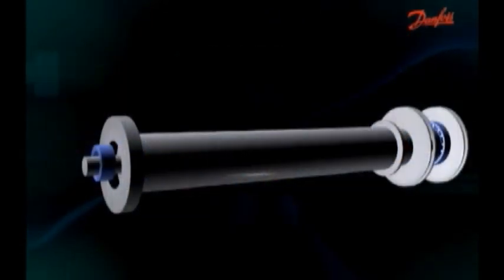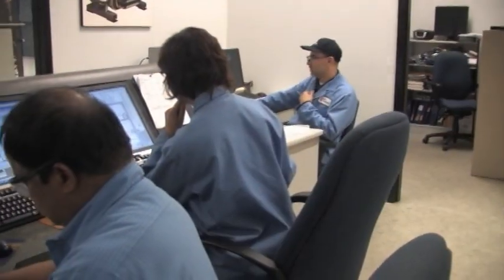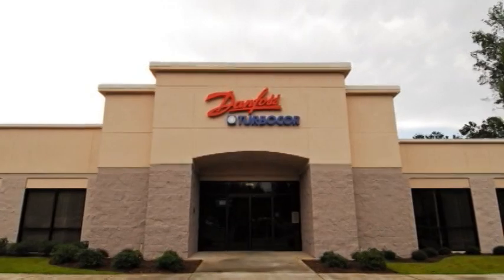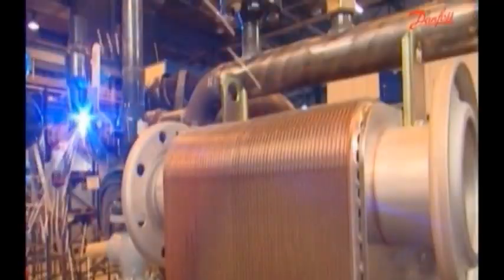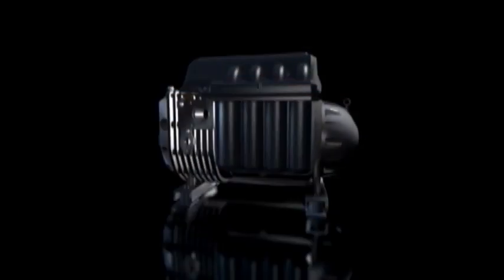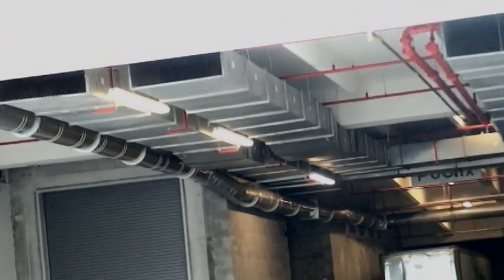The DTC compressor uses a magnetic field to levitate the shaft. There's no need for oil, and the compressor therefore uses less energy to start and to keep running. As a partial solution to today's energy challenge, a team of world-class experts, Danfoss Turbocor Compressors Incorporated, developed breakthrough technology in the design of an oil-less magnetic levitation VFD controlled centrifugal compressor for HVAC applications. By levitating the shaft, there's no metal-to-metal contact. With no metal-to-metal contact, there's no friction. With no friction, there's no need for oil or oil management systems.